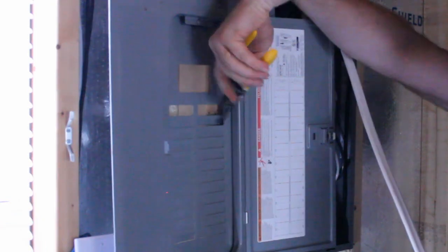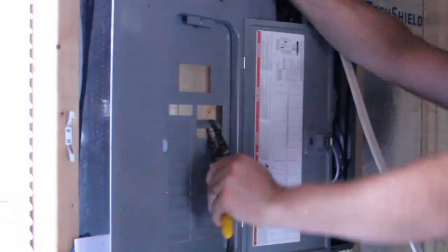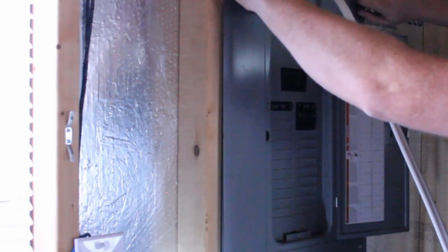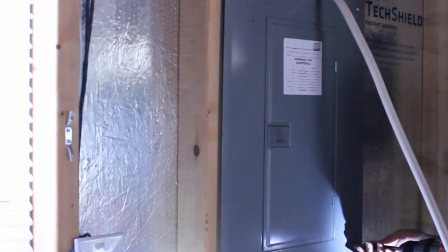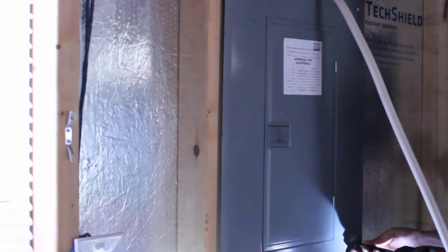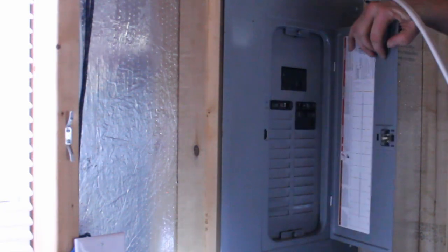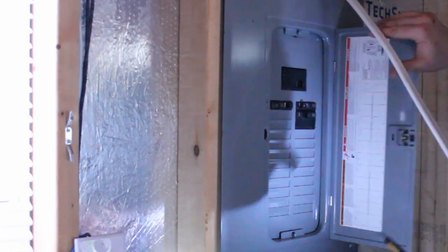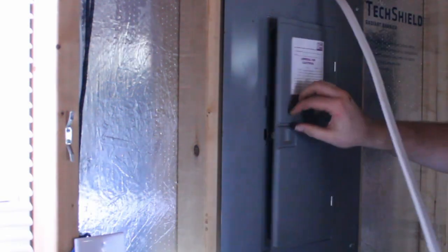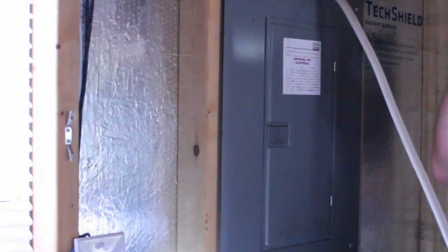All that remains to do in the panel is to remove the knockouts for the new breaker and put the panel cover back on. You might wonder why I started running this cable and making the connections in the electrical panel first, but because I did this project in the late afternoon, I wanted to make sure I could get all the work inside the panel done first so I could turn the lights back on to finish the work, while keeping the new breaker turned off of course.